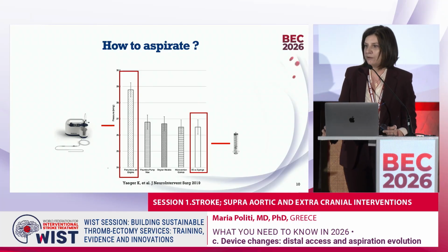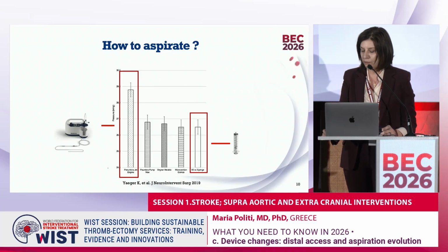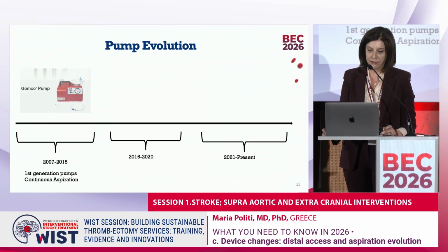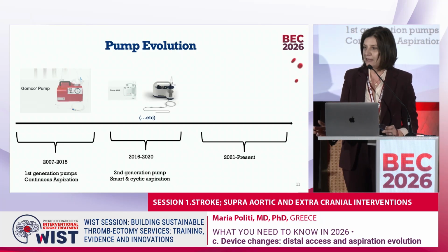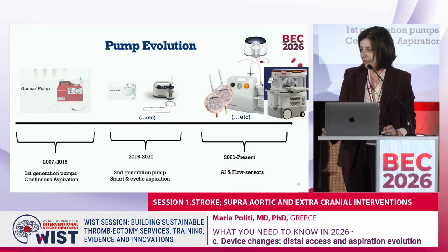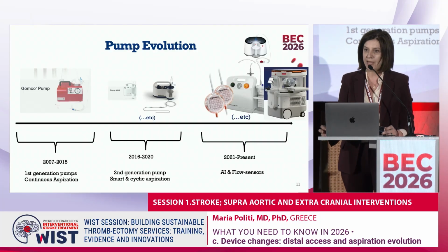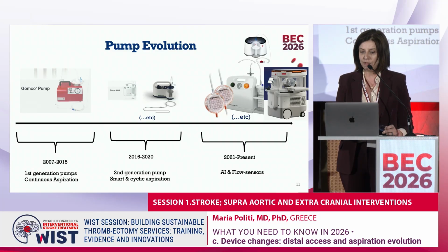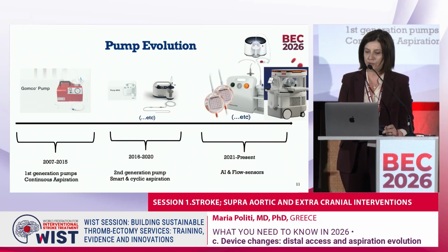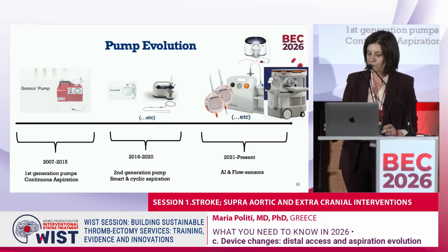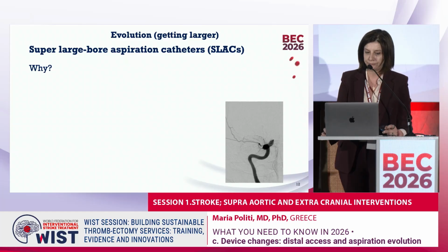How to aspirate? We have two ways. We can use a syringe or we can use a pump. There is also a great evolution regarding pump engineering, from continuous aspiration to cyclic aspiration, that has been shown to reduce the fragmentation of the clots. And now there are flow sensors where the pump stops aspirating when it notices that the aspiration tip is not attached to the thrombus, so it reduces blood loss during the operation.